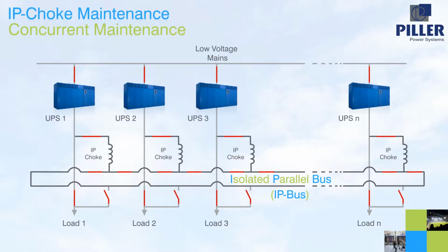Isolating the IP choke is just as simple. Firstly, the IP choke breaker is opened, and then the IP bus breakers around the IP choke are operated. The IP bus remains fully functional for the remaining UPS and their loads, and the load of the isolated IP choke continues to be supported directly with UPS power. Alternatively, the system can be designed so that the load in question is transferred to the IP bus before the choke is isolated.